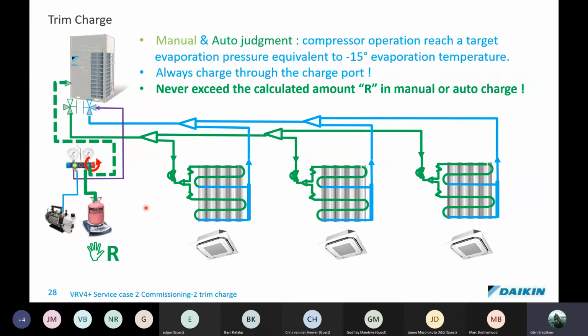Never ever exceed the calculated amount of refrigerant, no matter what method you are using for manual or auto charge. It's very critical that you keep an eye on this. And this is why you cannot arrive on site and do an auto charge without knowing the actual field piping lengths and having done the calculation. I've seen where systems have been put onto auto charge, how wrong it can go, and how it is easy to see how a system can overcharge itself through some factor that happened during the course of the charging.